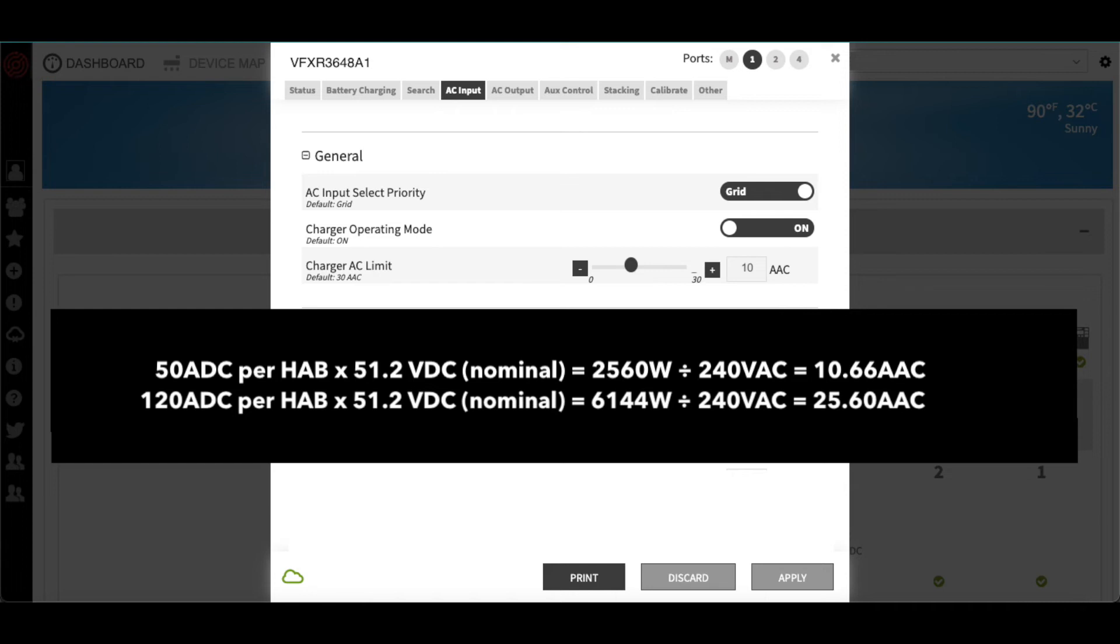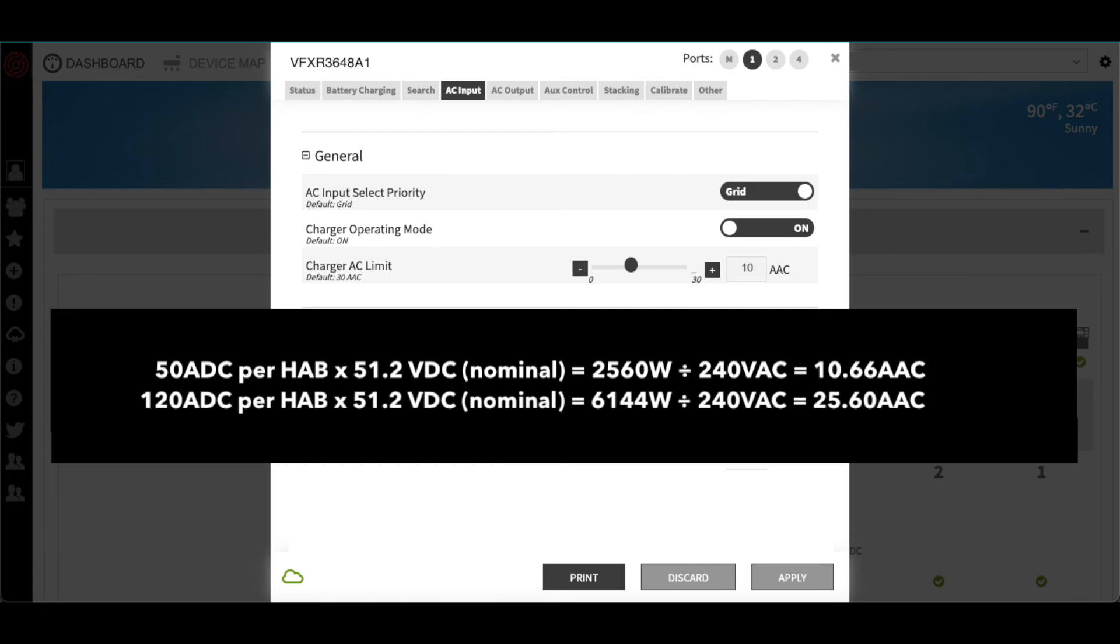To do so, we would multiply the permitted 50 amps DC per HAB by 51.2 volts, which is the nominal voltage of the HAB. This will show us how much power in watts we can use to charge the batteries. Then, we can convert watts to AC amps by dividing by our AC voltage, which in this case is 240 volts AC.